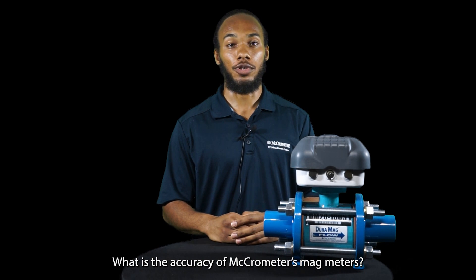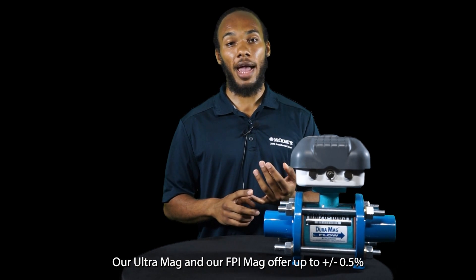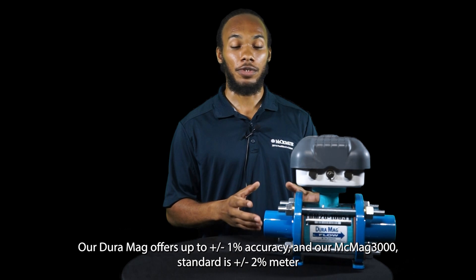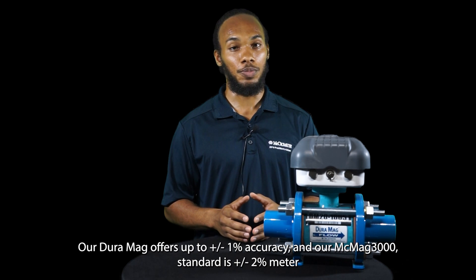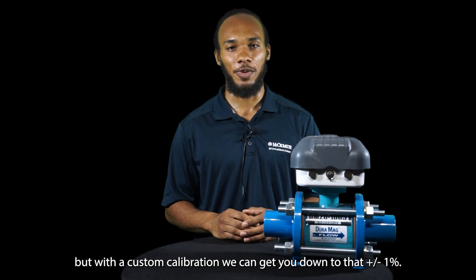What is the accuracy of McCrometer's MAG meters? Depending on your product, it may vary. Our Ultra MAG and our FPI MAG offer up to plus or minus half a percent. Our Duramag offers up to 1% accuracy. And our MCMAG 3000 standard is a plus or minus 2% meter, but with a custom calibration we can get you down to plus or minus 1%.